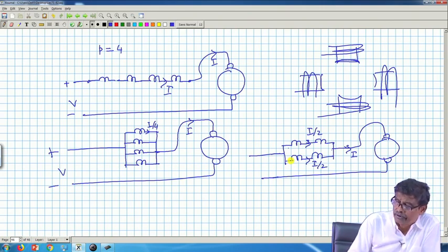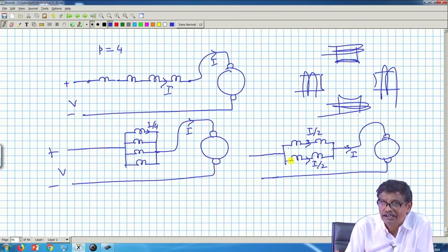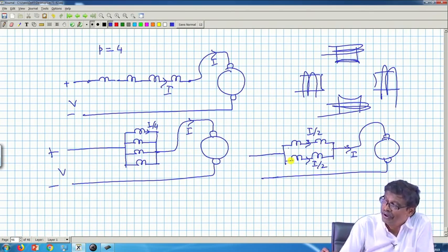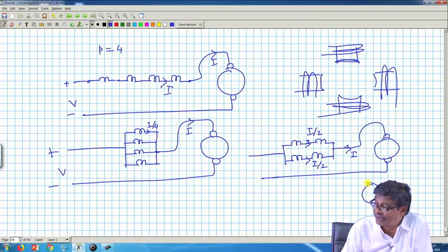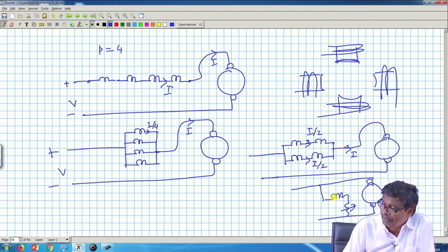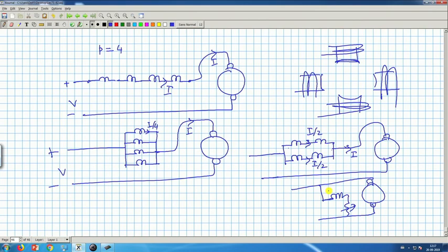One of the nice ways of doing it is this way, but it is not a smooth field current control as we did in the case of a shunt motor. In a shunt motor the connection was like this, and this is the resistance we controlled to decrease the flux per pole, that is all. But here, in discrete steps, some 3 or 4 levels of speed control are possible. You must keep this in mind.